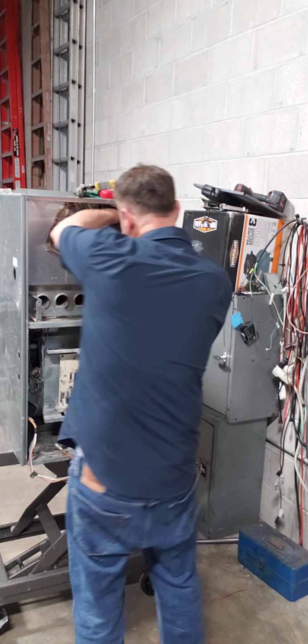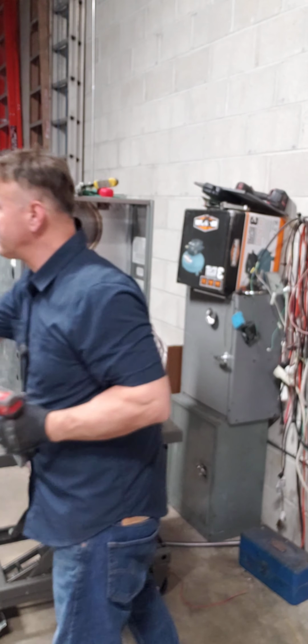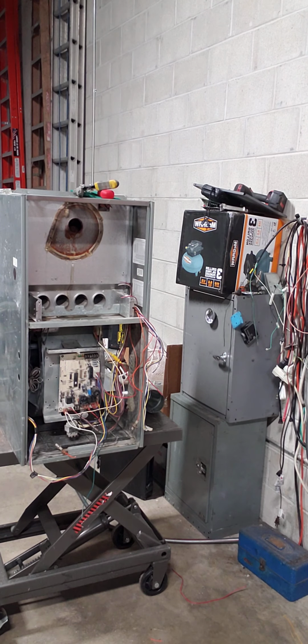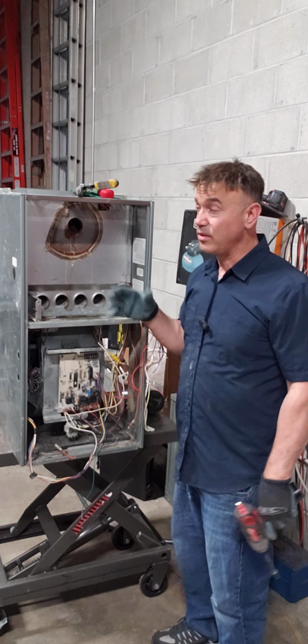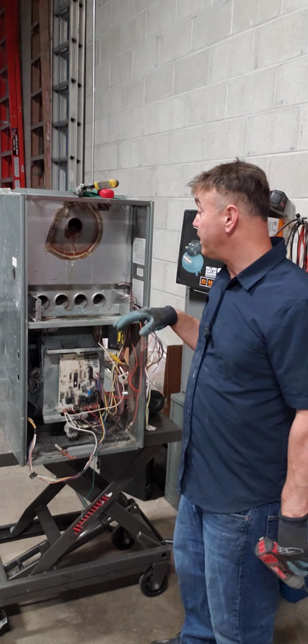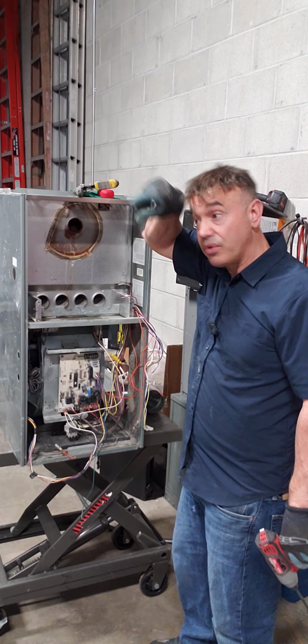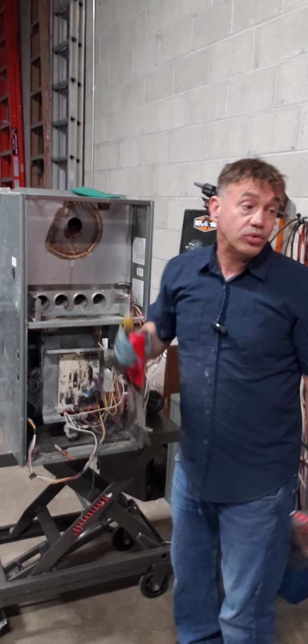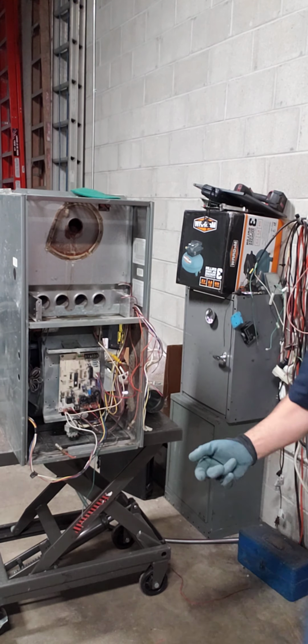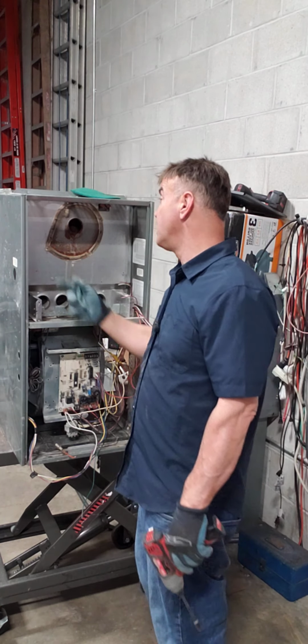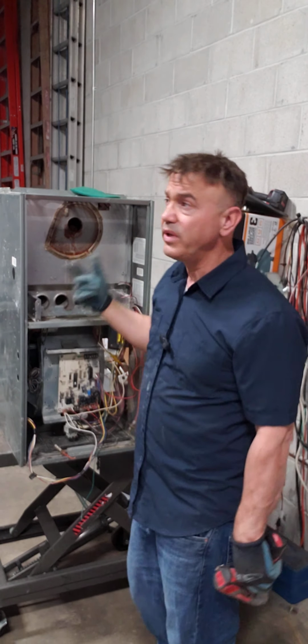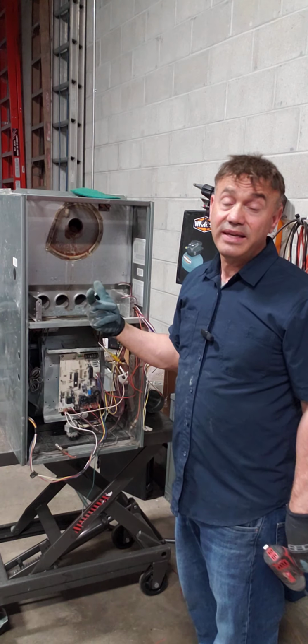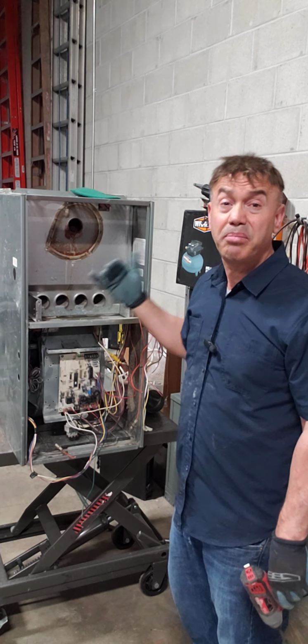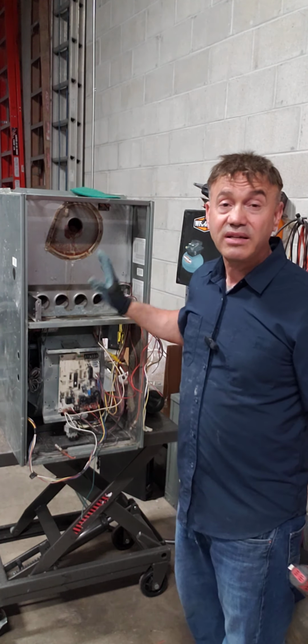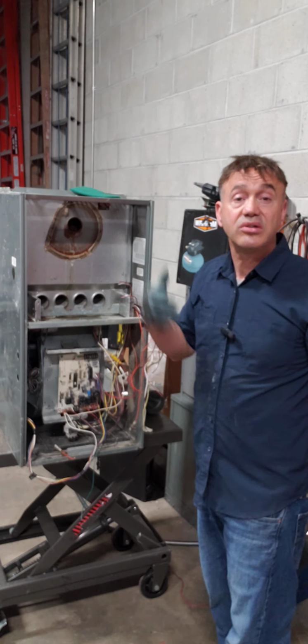My advice to you guys - there are many ways to go about this. I could honestly just replace the furnace since I know my job, but I will never replace a furnace as long as I can get a free heat exchanger under warranty from the manufacturer. If I go to Rheem now and tell them I need a heat exchanger for this furnace - this one is from 2002, already 22 years old - in most cases they can offer a lifetime guarantee. They give me a brand new free heat exchanger, I replace it, and the furnace can live another 20 years.